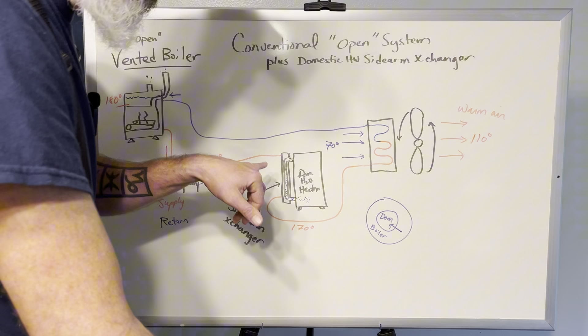So let's just say in this situation it's 170 - making numbers up just for even multiples of 10 - but the water will go into the sidearm heat exchanger, out of the sidearm heat exchanger, and then carry on to your heat. So putting your domestic water heater first in the loop.